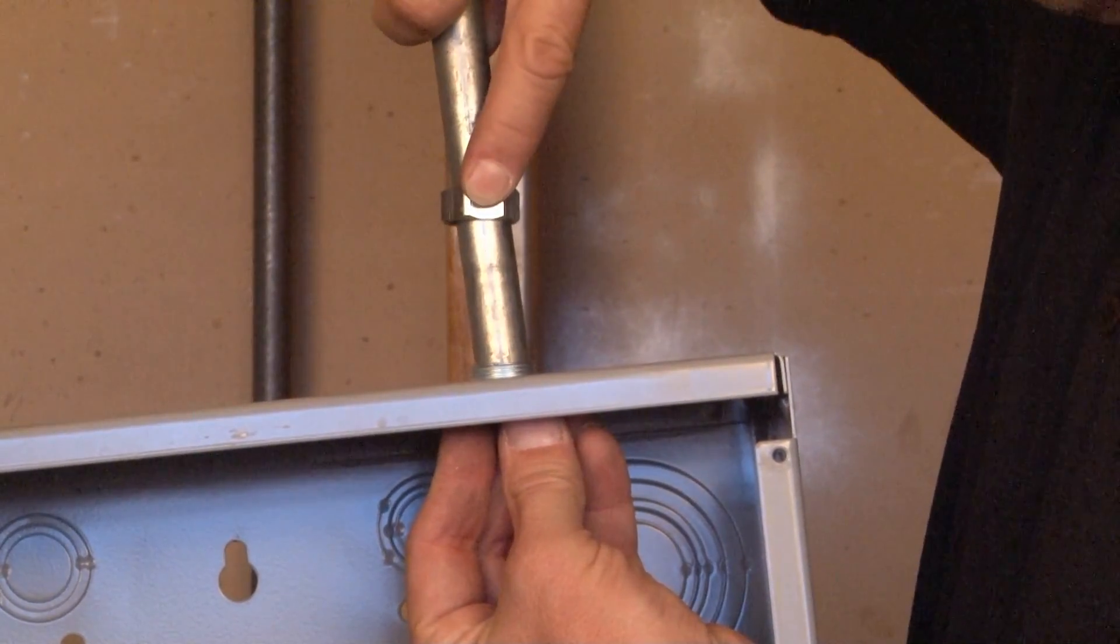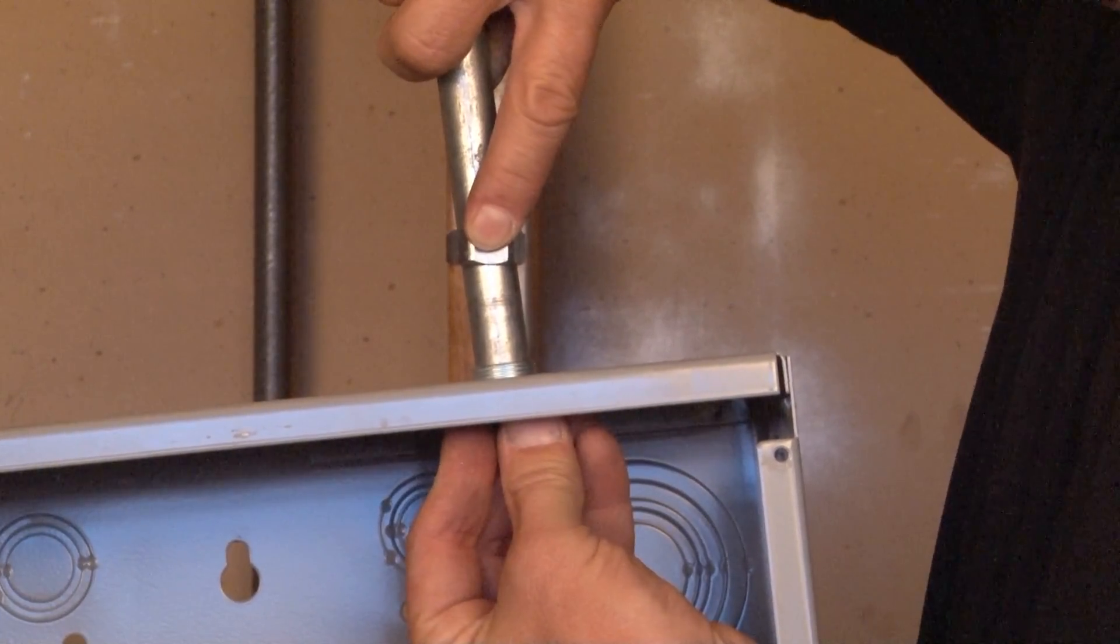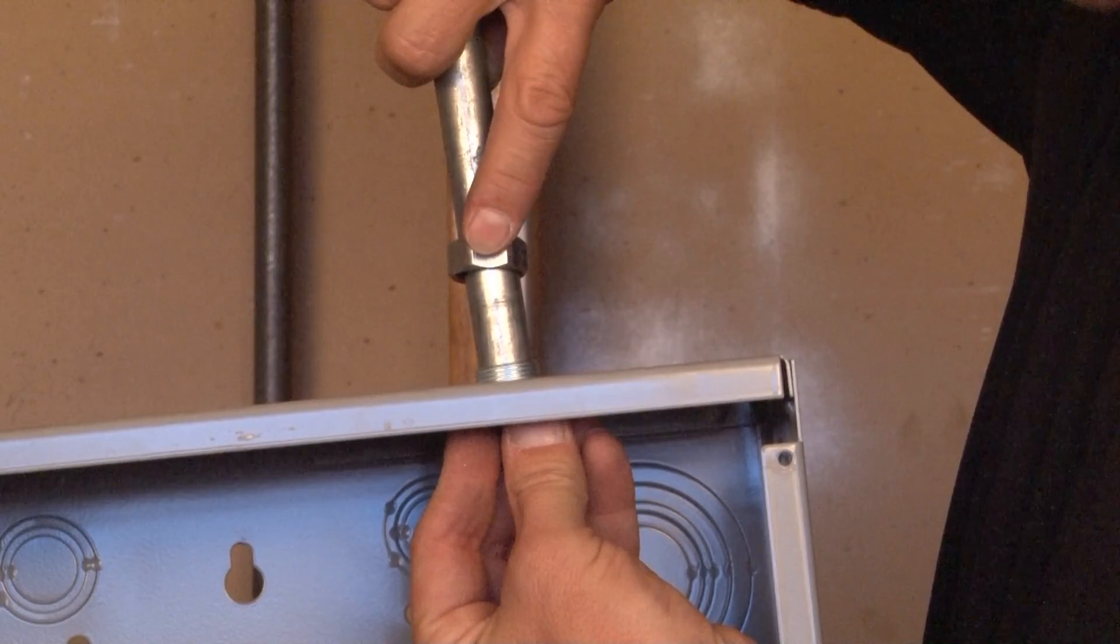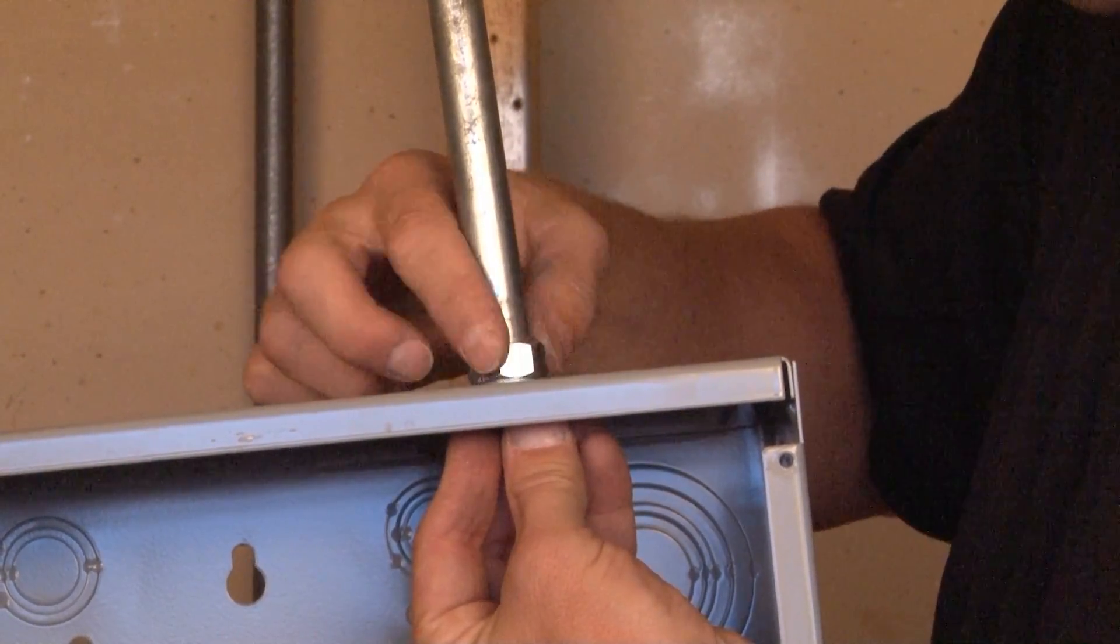At this point, you can drop in your EMT conduit until it catches on the stop. Now, drop the gland ring into place and re-attach and tighten it onto the threaded portion.